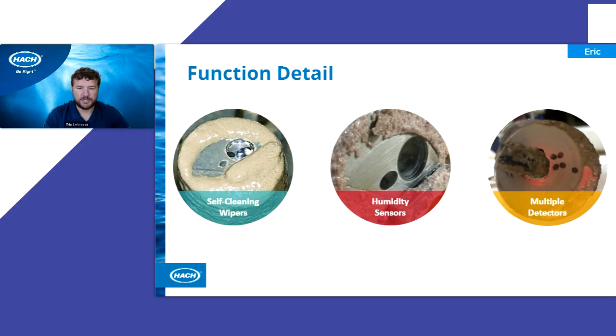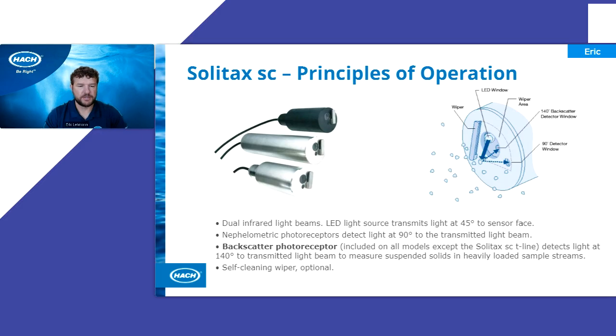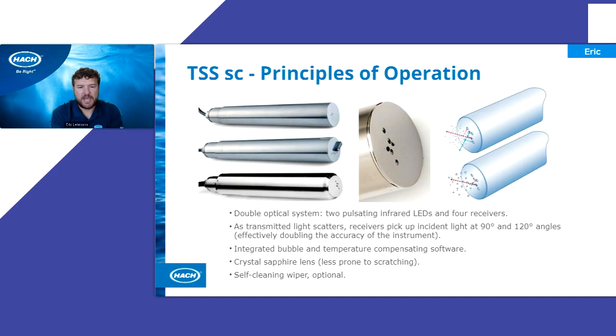I love these pictures here. They really show the effectiveness of the wipers on the probes themselves. There's a self-cleaning wiper, a built-in humidity sensor, and multiple detectors, which we'll get into here. So the principle of operation: how are we actually detecting turbidity or TSS using a probe? We use LED light sources to transmit the light. The Solitax uses a 45-degree light at the sensor face, a 90-degree transmitter light beam, and then a 140-degree transmitter light beam to detect the actual scatter of the light. The TSS SC uses 2 pulsating infrared lights and has 4 receivers versus the 2 receivers of the Solitax.